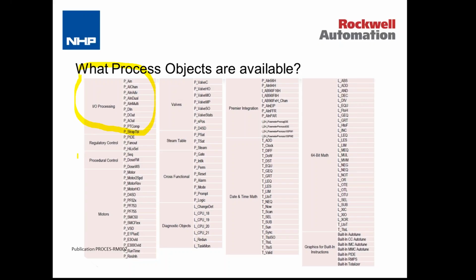procedural control. So we have some basic procedural control as part of the library. The library is centered around control modules and the objects, but we do have some procedural control. As you can see here, we have a simple sequencer. We have some dosing control for flow meters and for weigh scales. Then below that, you see that there's a range of objects for motors. So a range of DOL motors, single speed motors, two-speed motors, selection of variable speed drives, electronic overloads, and coming then into the next column, range of valves. So any valve that is typically used in the process industry is covered here.